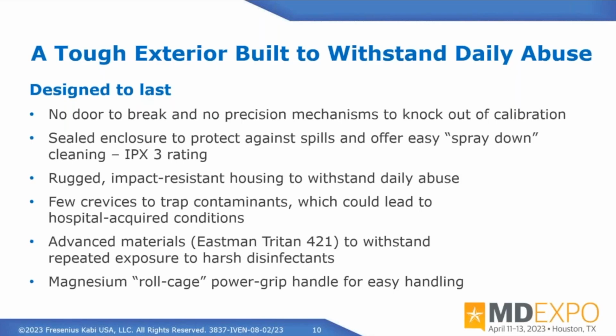And then the outside exterior is actually made of a polymer that will stand up to all of the harsh cleaners that your facilities are using to clean the devices. Our research showed that the plastics on the devices were failing because things like Cavicide were being used and they were tearing into the plastics, degrading the plastics and causing them to crack. So you can literally spray our device down directly all the way around. That's how you clean the device. You can scrub it with a brush, all of that good stuff. And you can use any of the normal cleaners that you might use today to fight things like C. diff and COVID and everything else that's happening in the world.